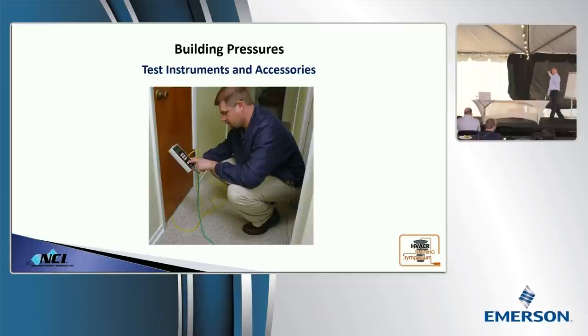So once you've seen that ball drop, you need to start taking some pressure measurements. This photo was taken a long time ago when I actually had color in my hair. Guys, you'll notice I've got a micromanometer and I'm taking pressures of the room, and I'm also taking them with reference to outside through pressure tubing. I'm seeing what's happening on the building side of the duct system. Basically, I am measuring static pressure on the building side of the duct system. I'm seeing what's going on there.